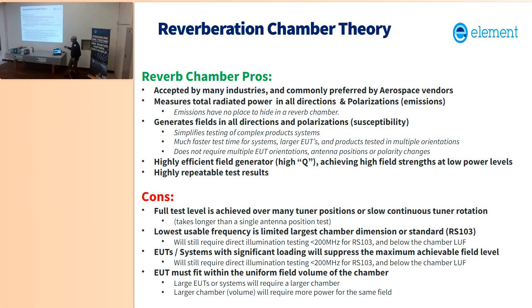The other pro of reverb chambers, like I was talking about, is you can get very high field strengths with relatively low power levels. And again, I can't emphasize enough, the highly repeatable results, whether it's emissions or susceptibility. And in Minneapolis, we have 4 different reverberation chambers, different sizes and shapes. One of them starts working at 1 gigahertz. So if you got a failure, we've tried this, we got a failure at, say, 2 gigahertz, we can repeat that failure within very tight tolerances in all 4 of the chambers, and they're all different sizes and shapes. And that's next to impossible in the anechoic chamber. That's really, really hard to do in the anechoic chamber method.